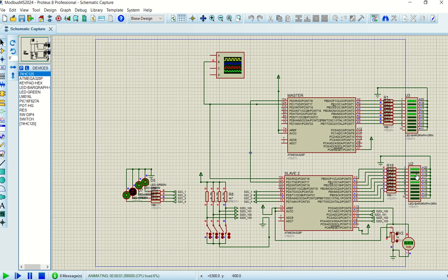There you can see it's E, that's 15, that's 15. There it's now requesting, and the slave unit is saying, listen here, function number 1 is now responding back, and as you can see here, look at this 1011, which is 1011. So this is function 1, which is now being transmitted back. So the master now knows exactly what's happening on the coils of slave number 2. And that, as we've seen, actually sits in an array by the name of coils in element number 0. That's where the answer sits.